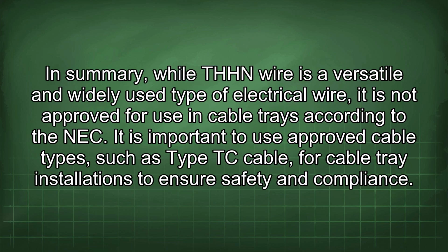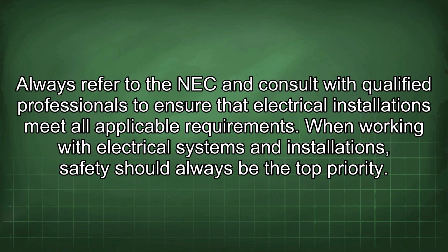In summary, while THHN wire is a versatile and widely used type of electrical wire, it is not approved for use in cable trays according to the NEC. It is important to use approved cable types such as Type TC cable for cable tray installations to ensure safety and compliance.